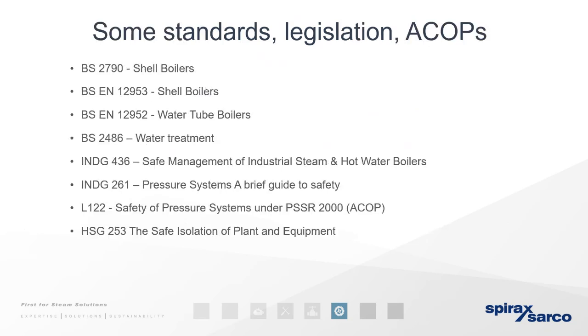So standards and legislation. So this again is more for the UK market. I know some of the European standards and British standards have been adopted throughout different areas in Africa. So this is more for reference. As you can see, they have the guidance notes there if you want to look them up. So it's BS 2790 for shell boilers. And you have BS EN 12953 for shell boilers, both British and European standard. BS EN, again British and European standard, for water tube boilers. BS 2486 for water treatment.